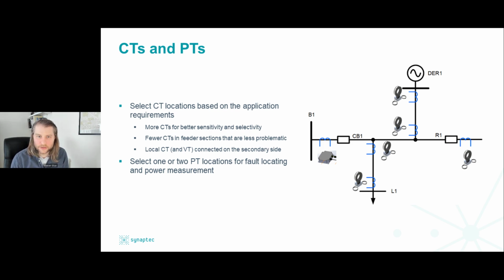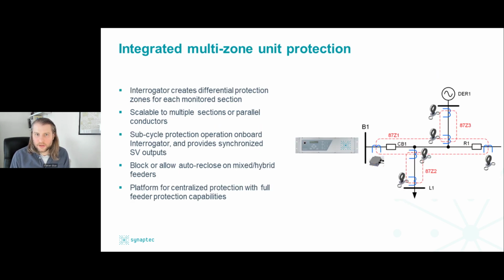And this is the holy grail of distribution protection, being able to pinpoint where faults occurred with high confidence, even with the complexity of DERs and other things going on in the circuit. As Neil's already given you a flavor of, the Synaptec interrogators can perform differential protection on board, and that can be done from multiple zones in real time on the device itself. And as you'd expect for differential protection, this provides sub-cycle operation for faults.